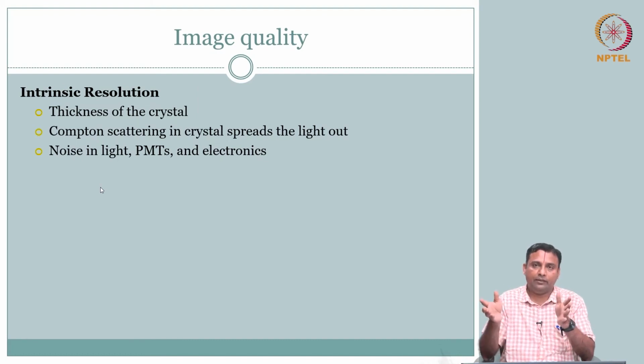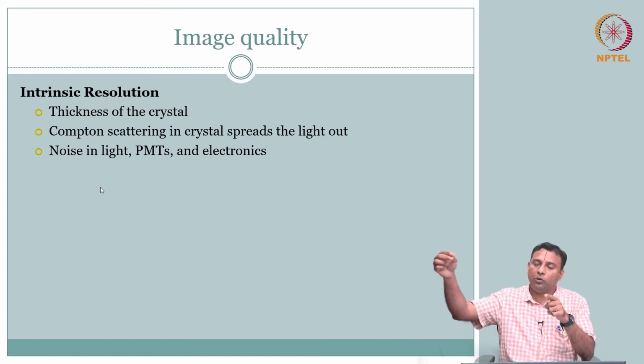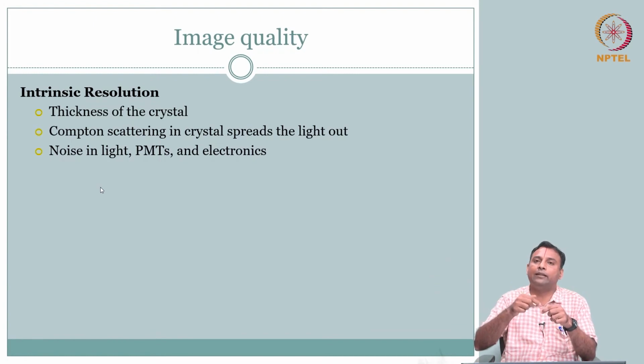That is it. We could not recover from that. Okay, it was directly the point spread of the intensifying screen that had an effect. Whereas here, the point spread similar to there is not directly recorded. The point spread goes and hits probably multiple photomultiplier tubes. So, you get the raw signal out, and then you use all this signal to calculate the x comma y.